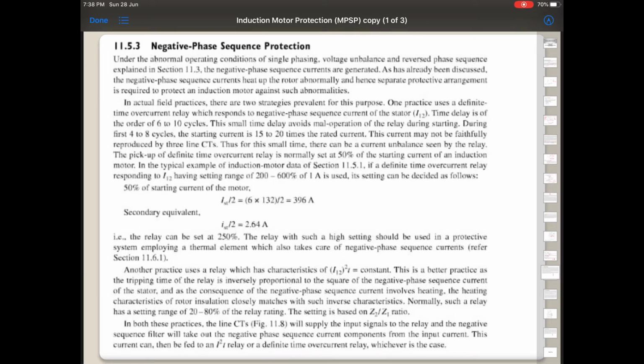and the setting is generally 2 to 6 times the rated current. So since it is taking 50%, the starting current is 6 times the rated current divided by 50%, we'll get this answer. 396 by 150, if you do, you'll get almost 2.64 ampere, which is nearly 250%. So 250% is set in the relay, because in a relay the setting is always in terms of percentage of the current.